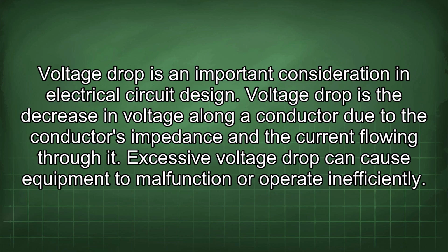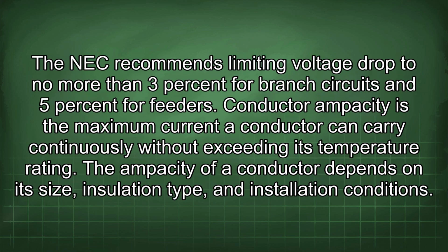Voltage drop is an important consideration in electrical circuit design. Voltage drop is the decrease in voltage along a conductor due to the conductor's impedance and the current flowing through it. Excessive voltage drop can cause equipment to malfunction or operate inefficiently. The NEC recommends limiting voltage drop to no more than 3% for branch circuits and 5% for feeders.